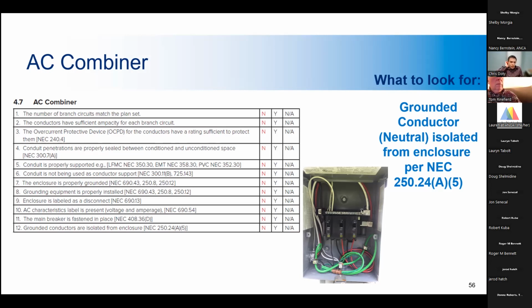So not only does the overcurrent protection need to be appropriately sized, which is these breakers here, the enclosure needs to be properly bonded and the neutral must be isolated from the enclosure. So in this case, the contractor did a good job of that. They isolated the neutral conductors from the grounding in the panel. You can see that all of the neutrals go to this neutral bar here, or lug, and then the grounding, the panel is grounded and the conduit is grounded as well.